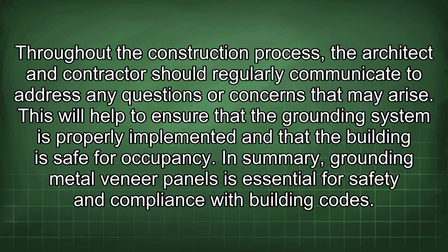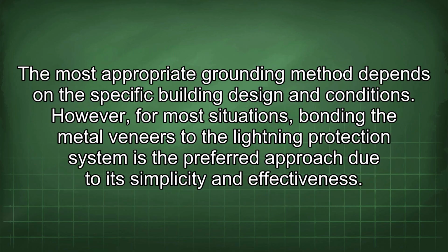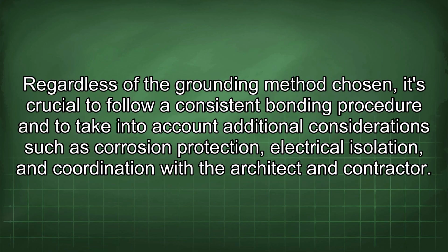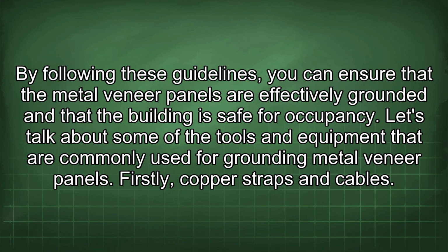In summary, grounding metal veneer panels is essential for safety and compliance with building codes. The most appropriate grounding method depends on the specific building design and conditions. However, for most situations, bonding the metal veneers to the lightning protection system is the preferred approach due to its simplicity and effectiveness. Regardless of the grounding method chosen, it's crucial to follow a consistent bonding procedure and to take into account additional considerations such as corrosion protection, electrical isolation, and coordination with the architect and contractor. By following these guidelines, you can ensure that the metal veneer panels are effectively grounded and that the building is safe for occupancy.